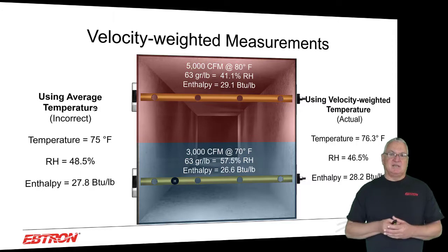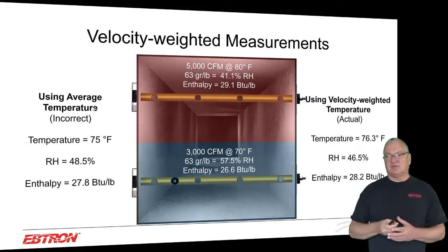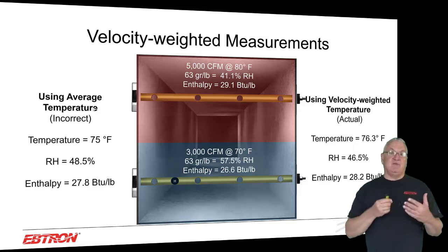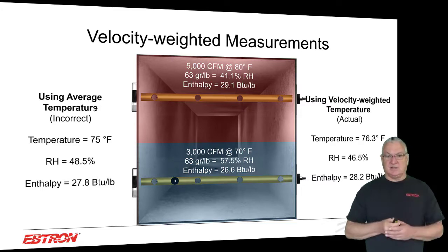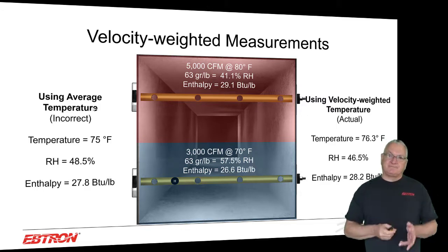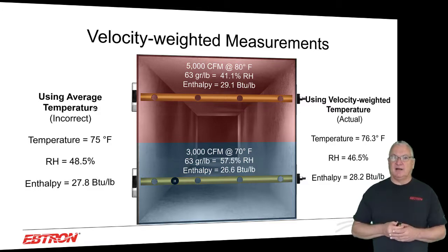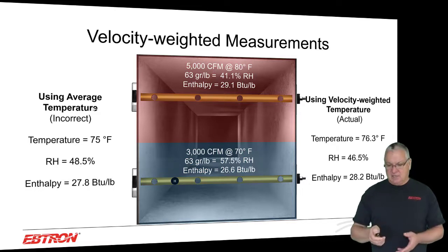And then enthalpy is the same type of thing. If you simply use the average temperature and a humidity sensor to calculate the enthalpy, you get 27.8 BTUs per pound. When using the weighted one, you'd actually get the true value of 28.2. And it would be even worse if you used a typical enthalpy sensor located in, say, the bottom of the duct there, where you can see it's 26.6 BTUs a pound. That's very important when you make the decision to go into economizer. On economizer switchover, you don't want to be economizing when you shouldn't be, or vice versa.